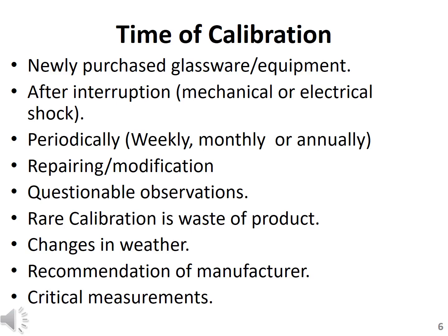If you are getting questionable observations, the readings you are taking or the results you are getting are questionable, not correct, not according to expectation, then you will be required to calibrate the instrument or equipment. And a very important thing is, if you are calibrating the instrument before the scheduled time, then you are going to waste a lot of time and a lot of money.